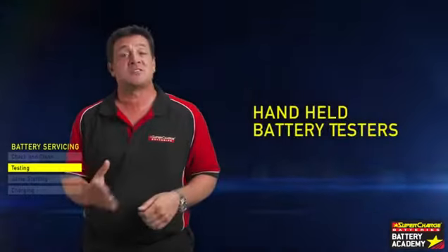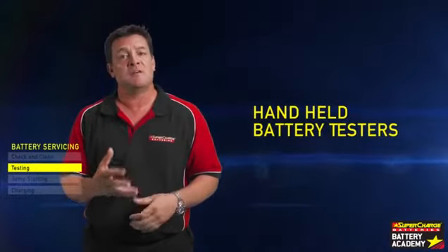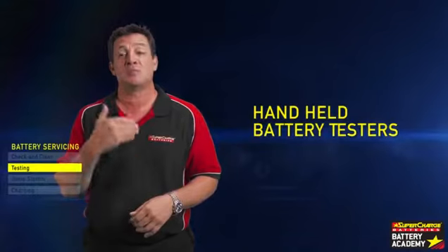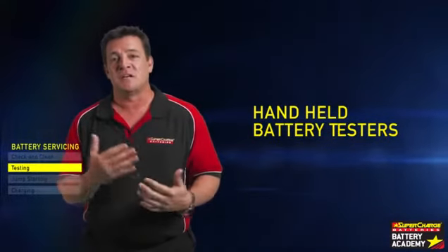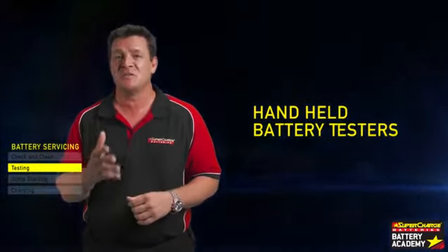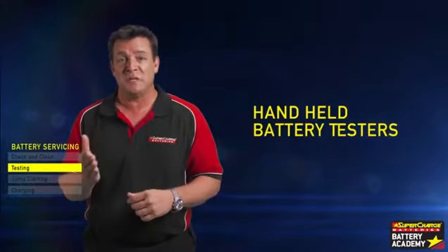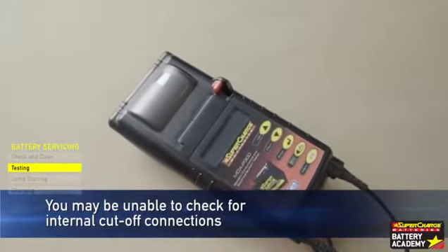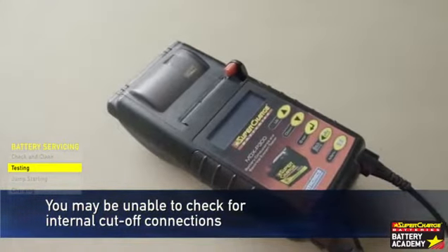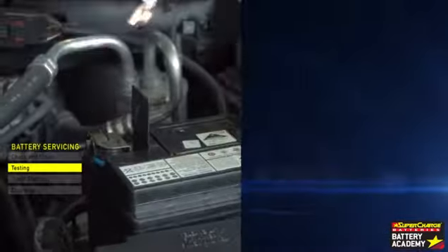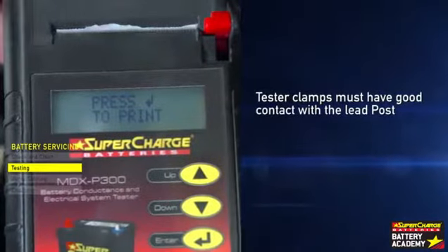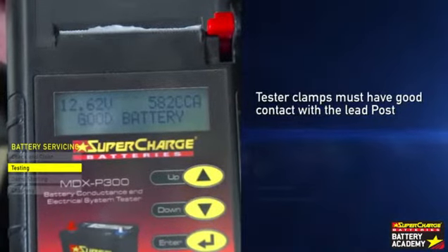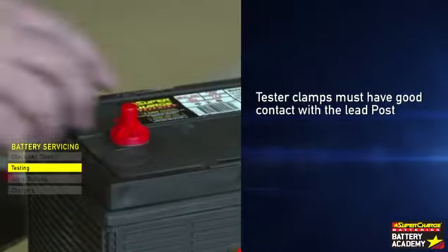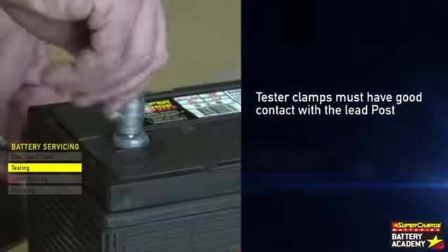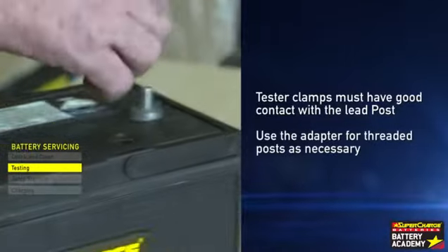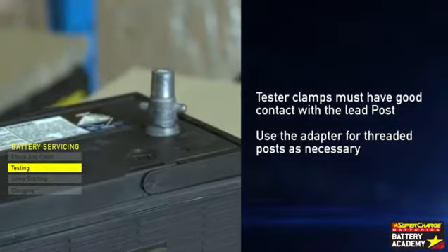Handheld battery testers such as conductance testers may be used if it is impossible to do battery testing using the recommended procedure, taking into consideration that there are limitations in doing so, such as the inability to check for internal cut-off connections, which causes a battery to fail once load is introduced. The tester clamps must have good contact with the lead post. Threaded posts on nuts may supply a false test result on most of the handheld testers. Use an adapter for threaded posts as necessary.